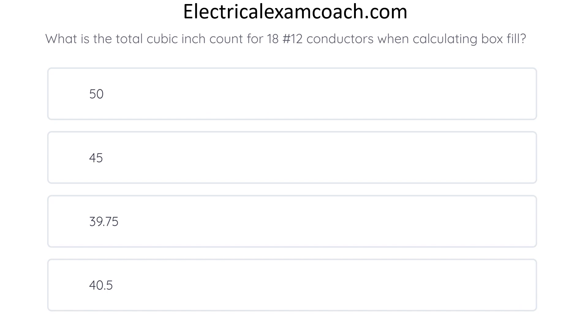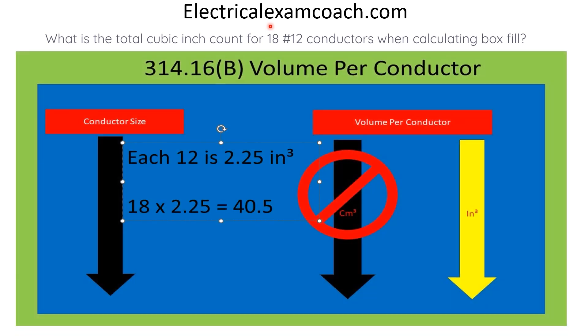What is the total cubic inch count for 18 number-12 conductors when calculating box fill? The correct answer is 40.5. To find this answer, we head to 314.16(b). We start on the left-hand side, find our size conductor, then come over to the cubic inches column. Each 12-gauge conductor is 2.25 cubic inches. We take our 18 conductors, multiply by 2.25 cubic inches, and we end up with 40.5 cubic inches. You can head to electricalexamcoach.com to learn about this subject and many more.